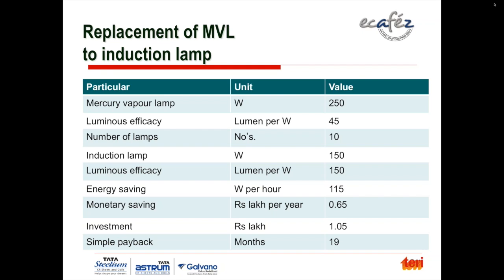Okay. So the LED lamp, as I mentioned, is good for a clean environment, but the induction lamp is typically good for outdoors and for factories with particulates, because when particulates deposit on the fins, the heat transfer reduces, and there are chances of LED failure faster than expected. So it depends a lot on the application, but the induction lamp is a very proven technology, and it is also manufactured within India. Philips also manufactures it, and Mahindra has a plant to manufacture induction lamps within India.